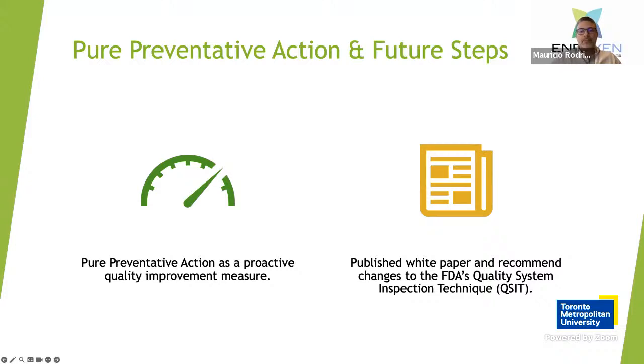So preventive action means, of course, the problem has never occurred before. And if you have ever tried to do a preventative CAPA, you know that you can't really assess the risk. And you can't really do an effectiveness check because it's very complicated. So firms usually struggle with that, right? Like the effectiveness check of a CAPA, as we saw in the step-by-step process breakdown, you have to demonstrate that your CAPA has been able to effectively eliminate the root cause of the problem. When you're doing a preventive action, as in the PA part of the CAPA, it's really hard to come up with an effectiveness plan to demonstrate that the issue that hasn't even occurred is going to be effectively resolved by the exercise that you're doing.